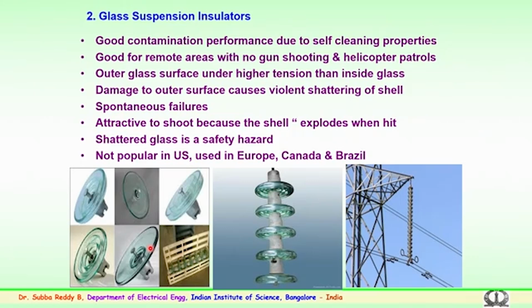So, that was about the ceramic or porcelain insulators which we have seen. A quick look at the glass suspension insulators. Again, glass insulators are very old, almost similar to the ceramic or porcelain. They have good contamination performance due to self cleaning properties and they are good for remote areas, particularly with no gun shooting or helicopter patrols, where some people shoot the glass insulator for fun, where the insulator sheds shatter and the insulation level decreases.